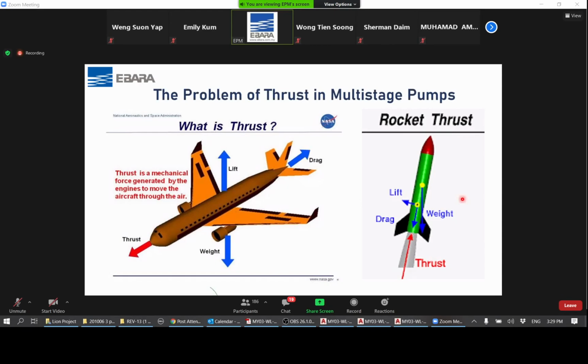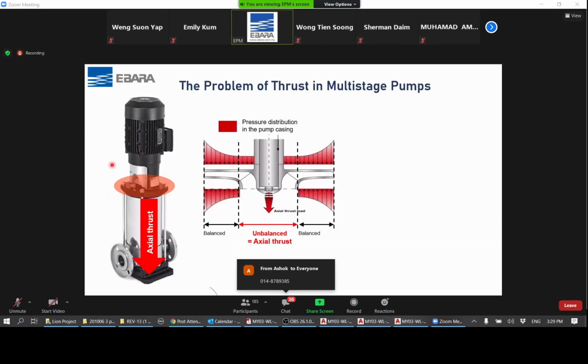But if we come back to the subject of a multi-stage pump, a multi-stage pump will have a lot of what we call an axial thrust. Now, I mentioned earlier how these pumps operate, where water goes into the pump and the pressure is built up in each stage. If you look at the stage of each pump, you will see that the red zones are what we call the pressure distribution. So this is the bottom of the impeller where the water comes in. Whenever the pressure builds up to the next stage, there is a higher pressure on top of the impeller compared to the bottom of the impeller.